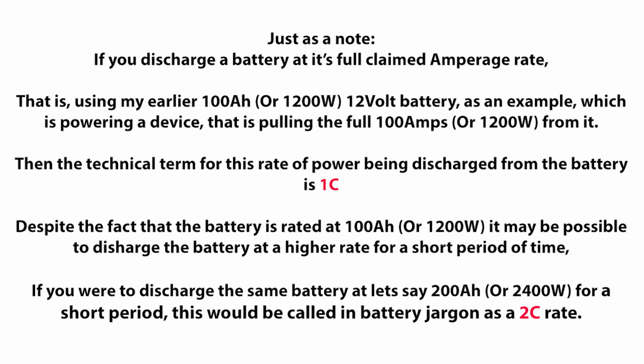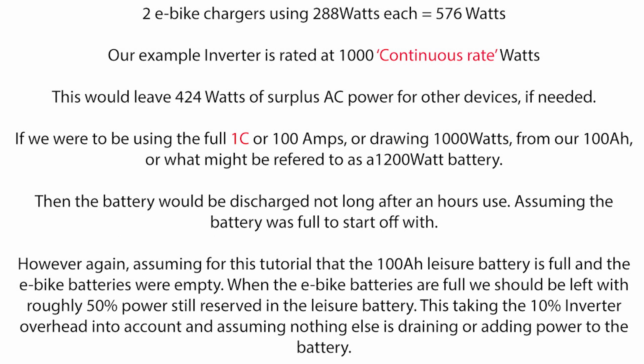twice its C rate, like 2400 watts. This would be considered a 2C discharge. That would theoretically discharge the battery in about 30 minutes. See where I'm going here? So, back to the simple maths. 576 watts for both e-bikes charging would leave us with a surplus of 424 watts for other devices that you might plug into the 230 AC socket simultaneously.